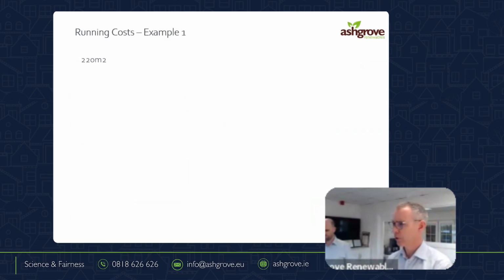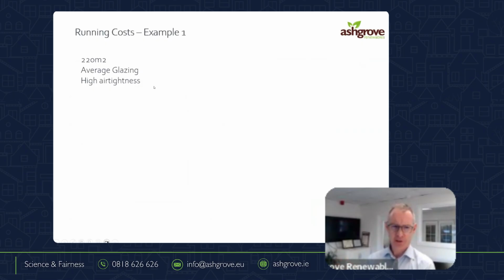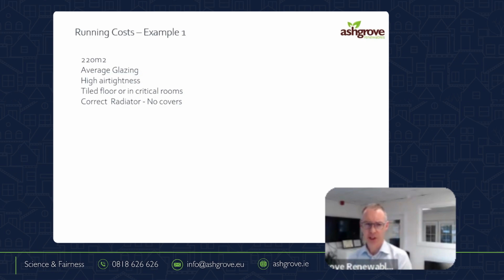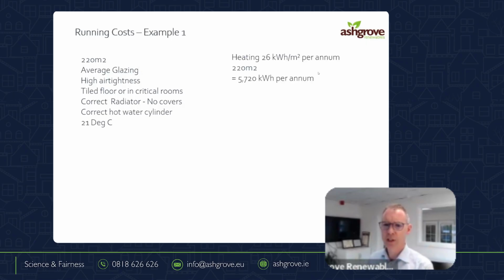So I want to give, and I'm not going to spend time at this because Johnny thinks it's beneath us. We're going to take a running cost example of a house here, 220 square meters, average glazing, high air tightness, tiled floor. So this is a well insulated house, and everything is right. Okay, with the correct radiators if it is radiators, and we don't have any coverings on it. We actually have no problem with radiators. In fact, in a lot of cases, I prefer to see radiators because if they're too small, we can change them. If the underfloor heating is badly done, we can do nothing about it. So I'm nearly at the point where it hurts me to say it, that I nearly prefer if somebody comes to us that they have radiators, because I have no faith in the underfloor heating design. And we're assuming the cylinder is correct and all the rest of it. But the running costs are calculated like this.